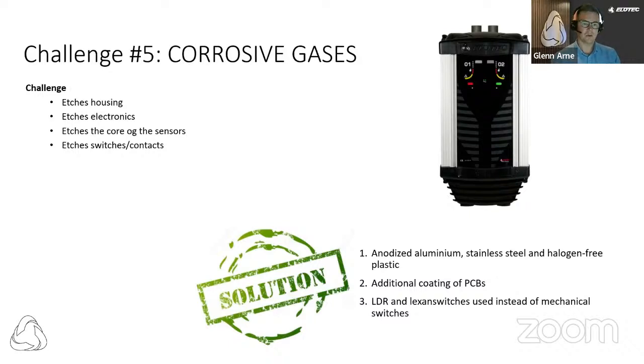And another challenge is corrosive gases. It can etch the housing, etch the electronics, etch the core and the sensors, and etch switches and contacts. And we don't want anything of that, do we? And Elotec's solution to that is anodized aluminum, stainless steel, and halogen-free plastic. Additional coating of the PCBs will protect the PCBs, and LDR and Lexan switches are used instead of mechanical switches. That means when you open the door on the Elotec Aspect, there isn't a switch to turn off the fan. It's an LDR sensor that when light hits it, the fan will stop automatically.